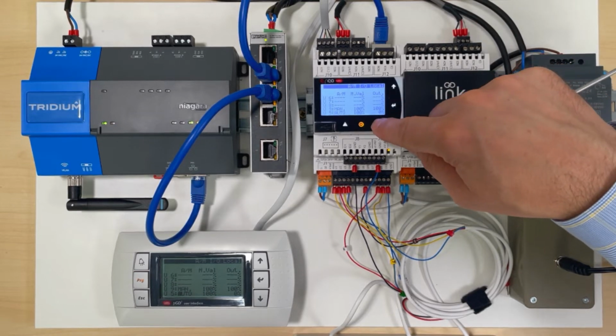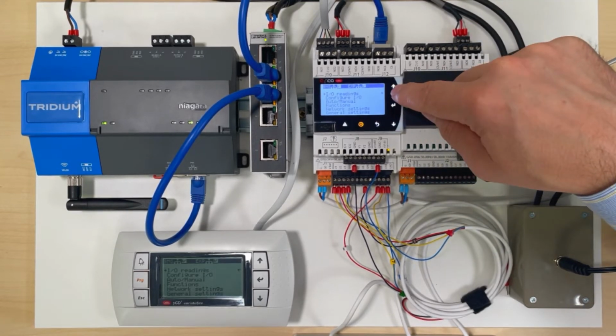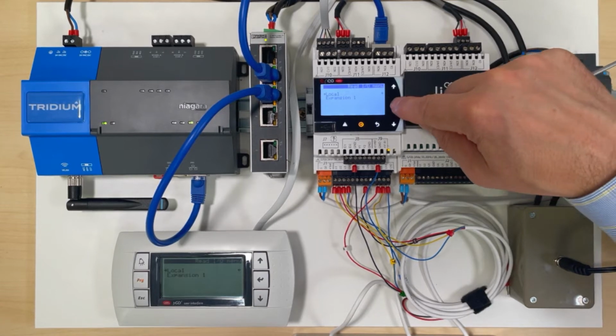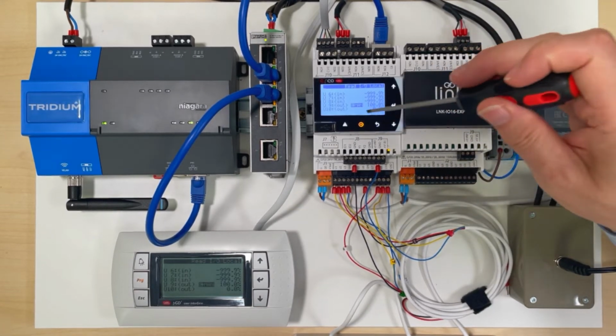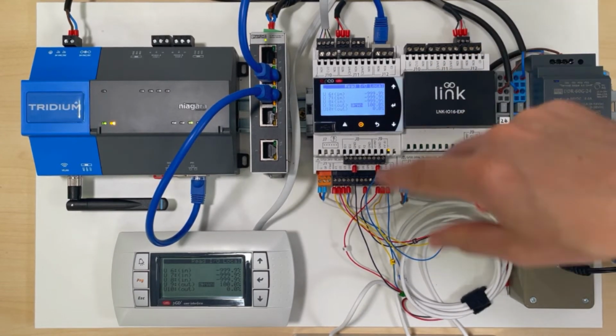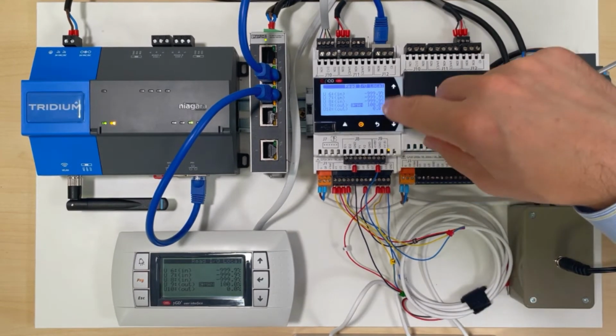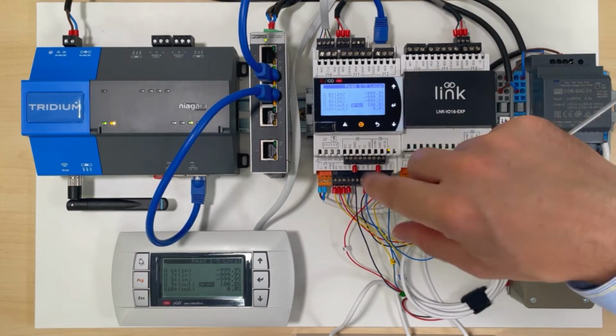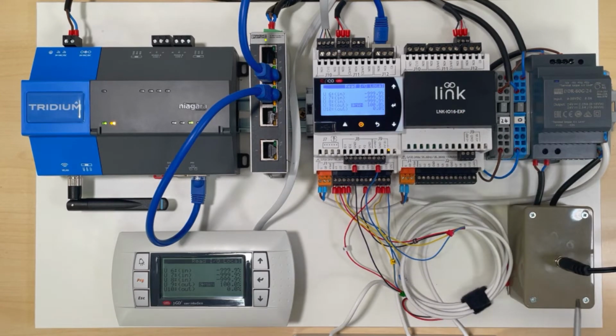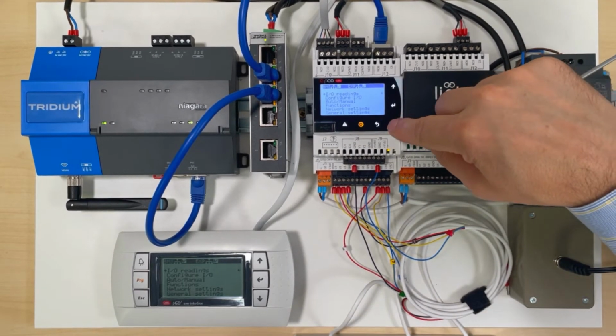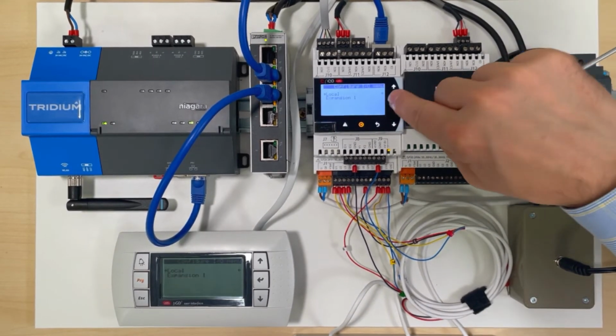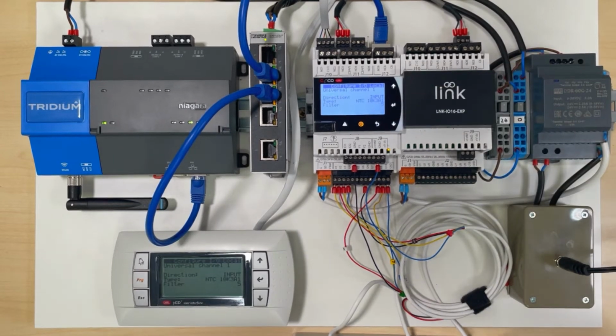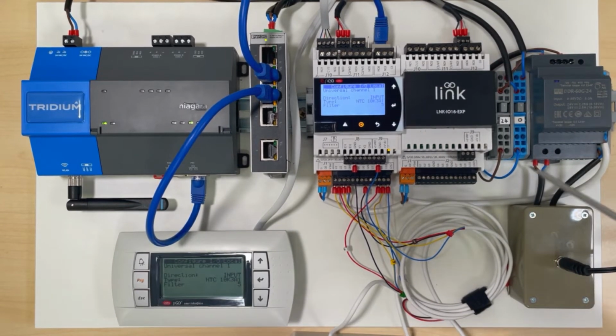And then if we go back now to our IO readings, if we go down there now, what you'll notice is a flag that says you're in manual. Okay, so it's a good way of alerting people that things are not in automatic when they're doing servicing and checking faults and things like that. So let's have a look at the configure IO menu. Like I say, there is a web configurator that's a much better way of doing this, much more convenient, but you can do it from here.